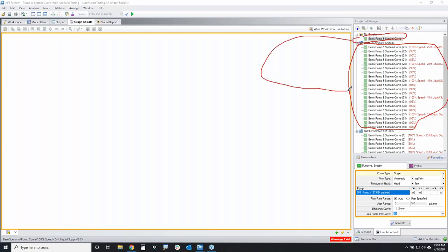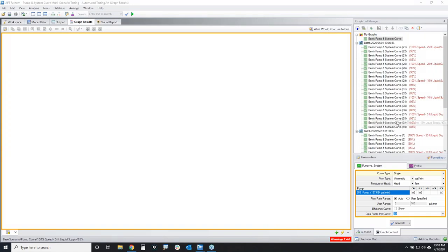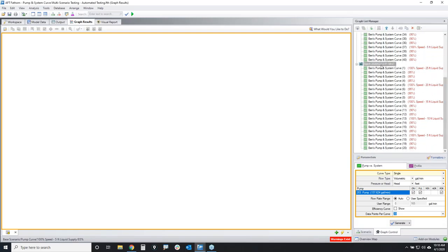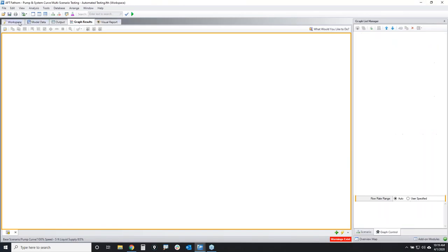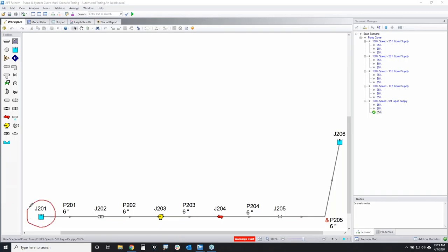I've actually done this batch run twice — once on February 13th, 2020, and the latest is today, April 1st, 2020. In the Graph Results window you can see a whole bunch of graph list items — the initial graph list item was recreated for each individual scenario during the batch run. During the batch run it would run the model, generate the pumping system curve, and store it one after another for each scenario. Now I want to show all of those system curves on the same plot — showing the different curves when I change my supply level from 25 feet down to 20, 15, 10, and 5, and showing pump curves for 100%, 95%, 90%, and 85% speed.